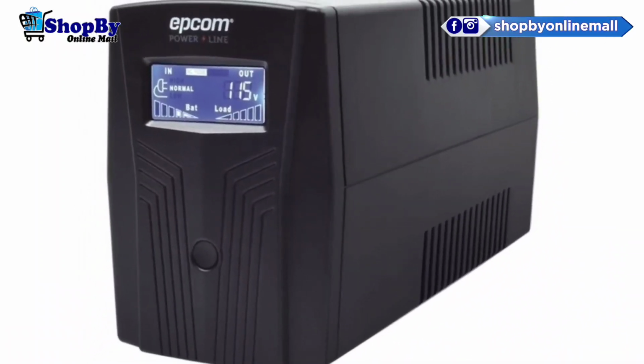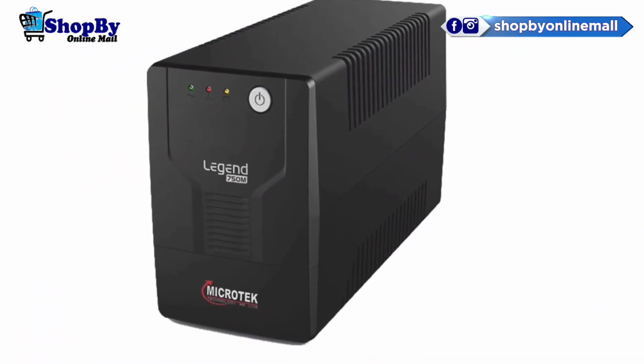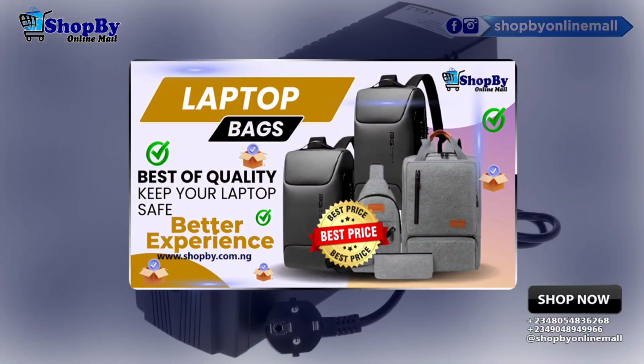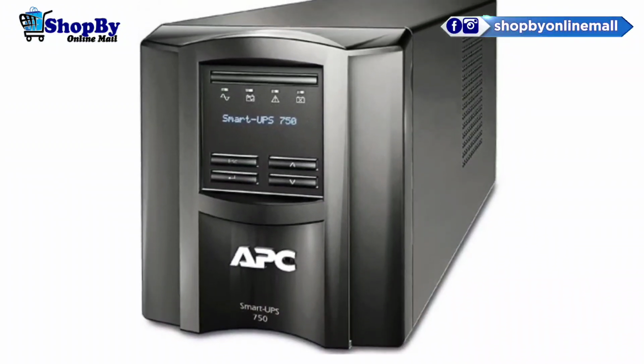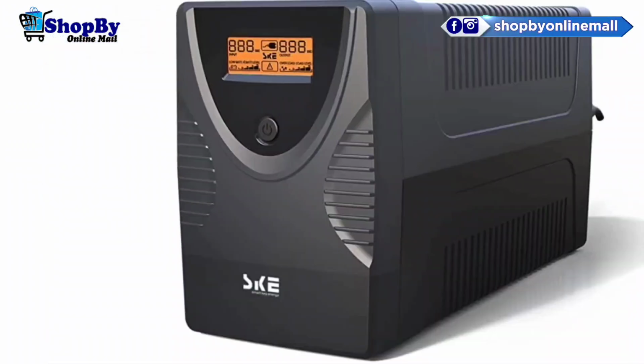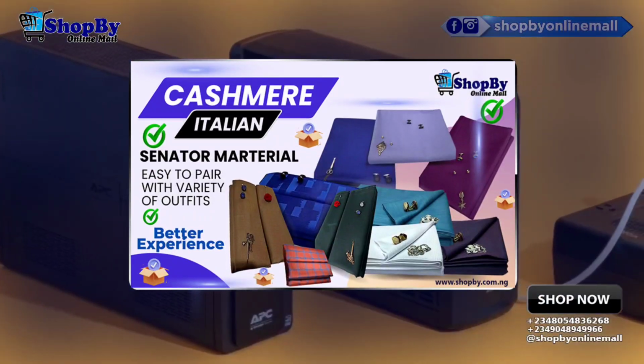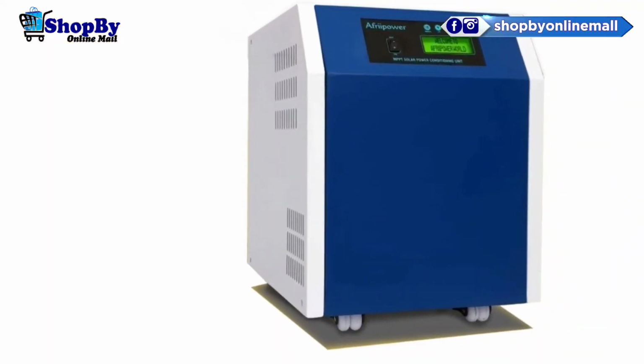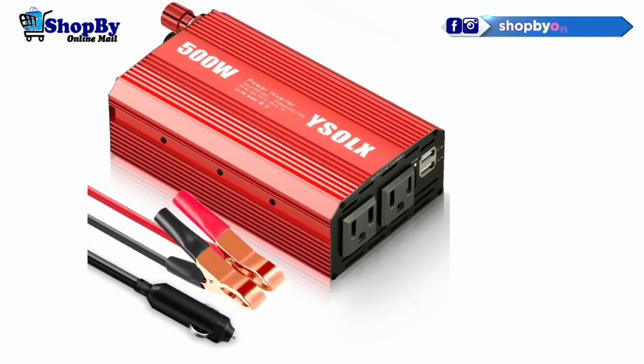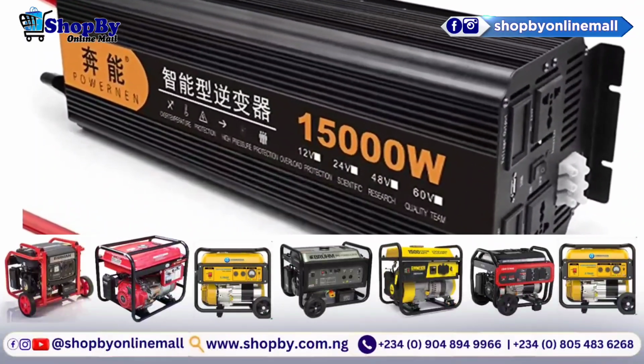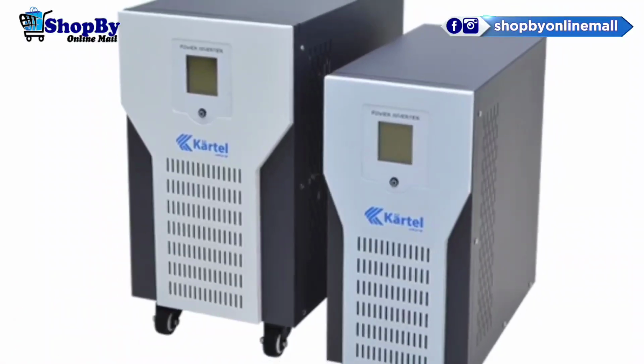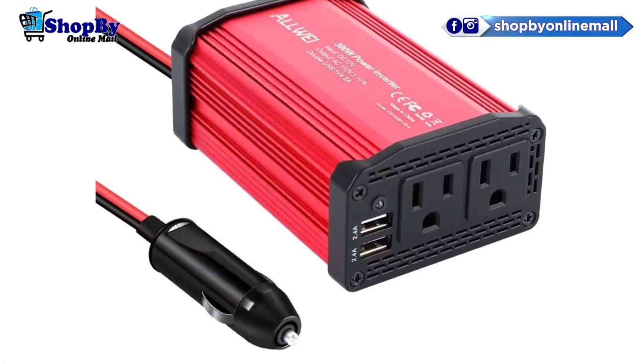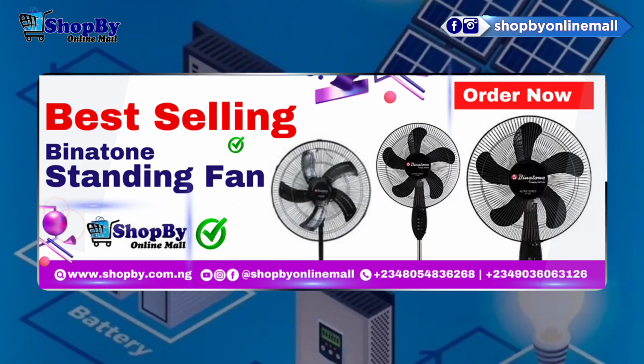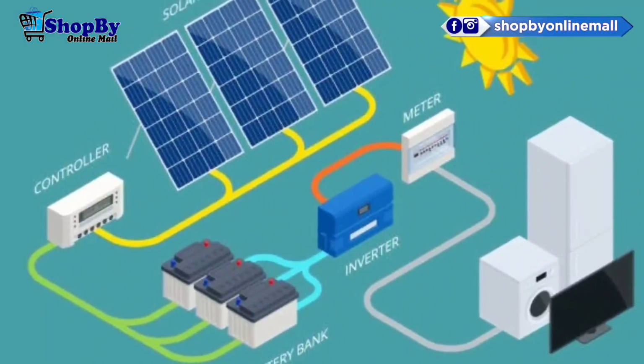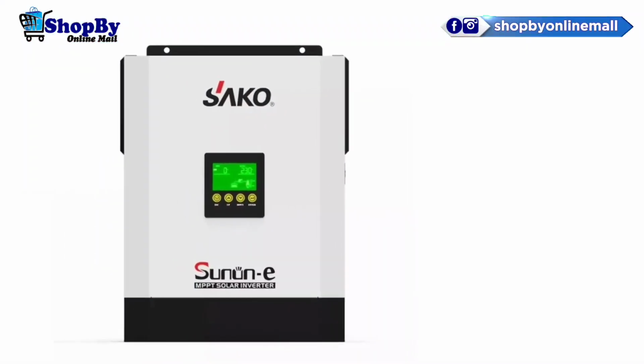Here are some differences between UPS and inverter. The main function of an inverter is DC to AC power conversion, while a UPS is backup power with no interruption. Many inverter models can use external storage, while a UPS includes built-in storage and add-ons to extend battery time. Inverter response speed is around 500 milliseconds, while a UPS is less than 10 milliseconds. Inverter power input is only DC, requiring a charge controller to fill batteries with AC power, while a UPS has AC and DC options. Inverter output connections have only AC terminals, while a UPS normally includes receptacles to connect appliances directly.